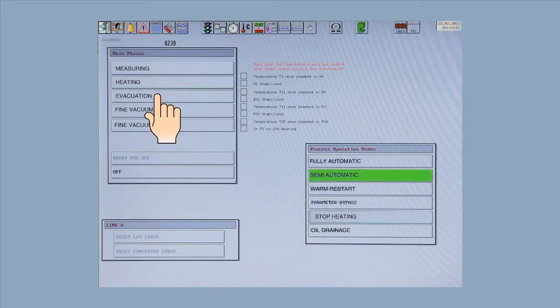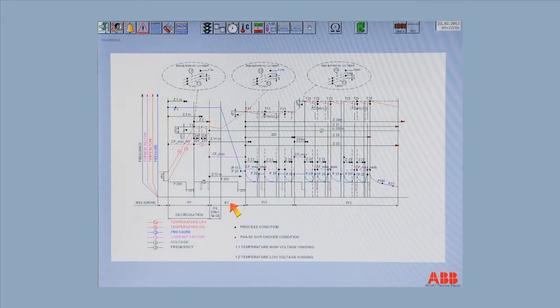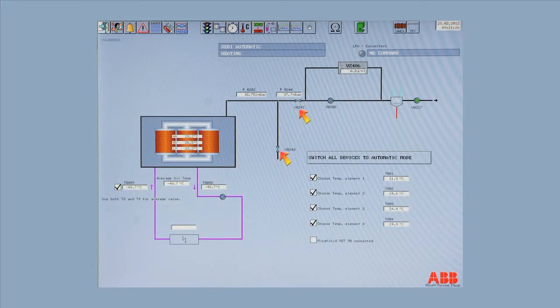Evacuation step. The operator can initiate the evacuation step by pressing the virtual button on the control screen called Evacuation. At that point, if the transformer was filled with heated recirculating oil, the oil is pumped out of the transformer. If the heated oil is being sprayed and circulated, then that part of the process continues on into the fine vacuum 1 stage. The main vacuum pumping system and the booster pump are turned on.